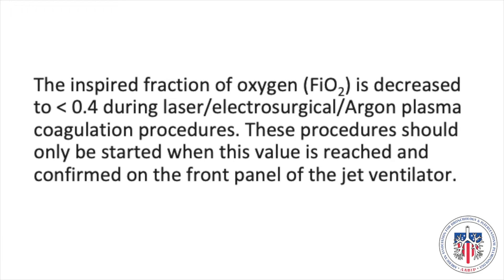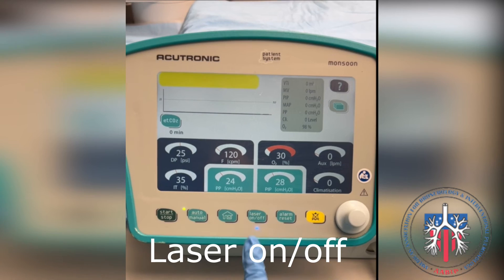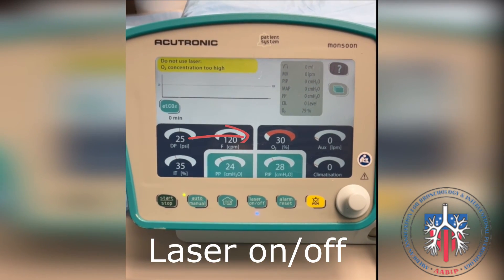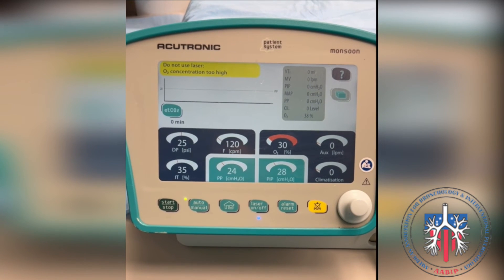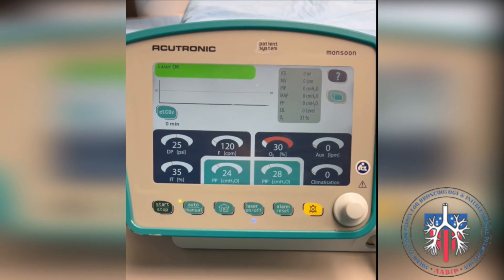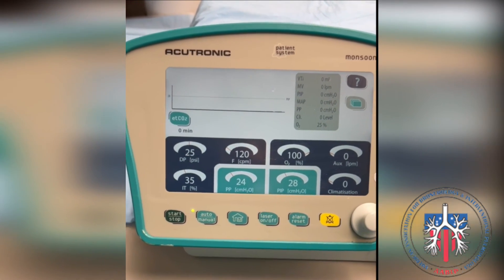The FiO2 is decreased to less than 40 percent during heat ablation procedures. These procedures should only be started when this value is reached and confirmed on the front panel of the jet ventilator. To reduce the FiO2, press the laser on-off button. The FiO2 will reduce to 30 percent. To increase the FiO2 back to 100 percent, press the laser on-off button.